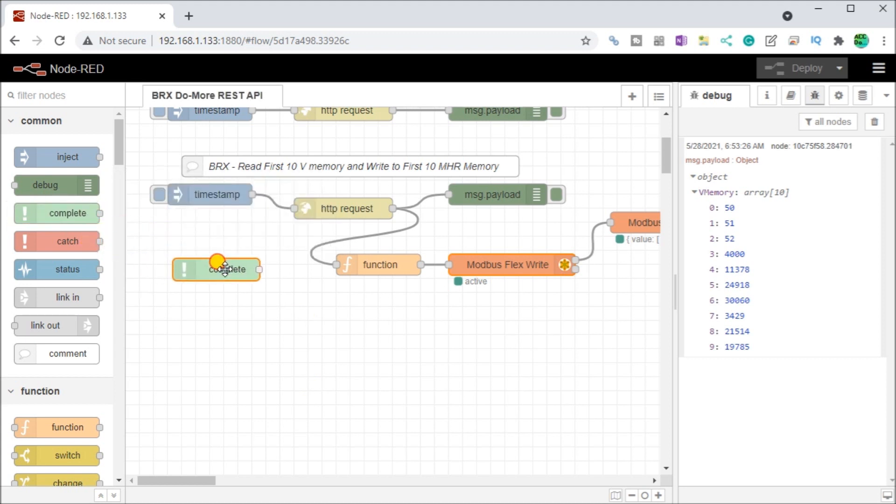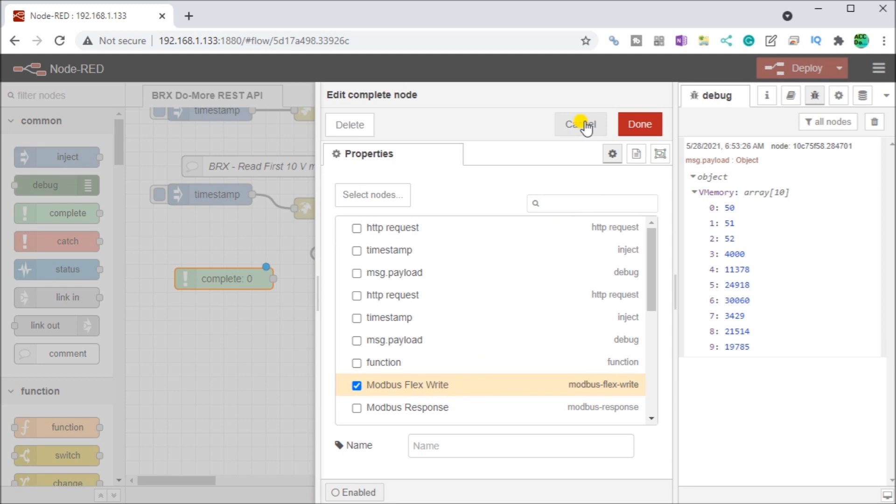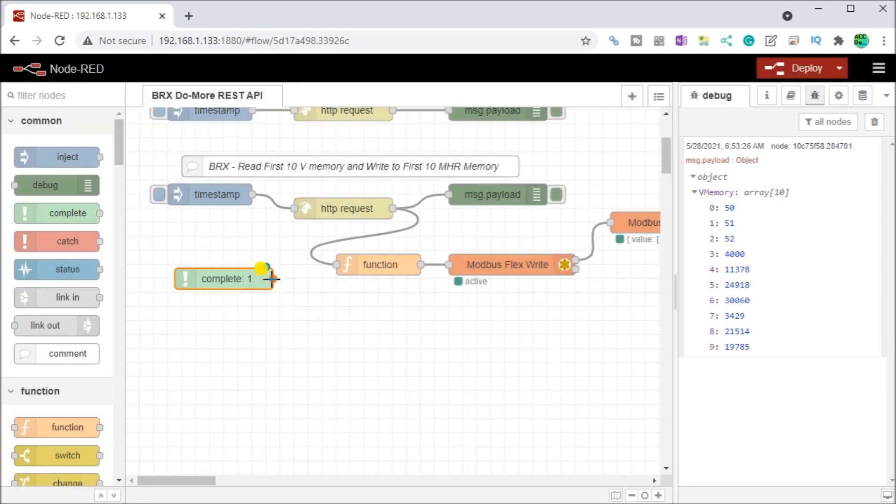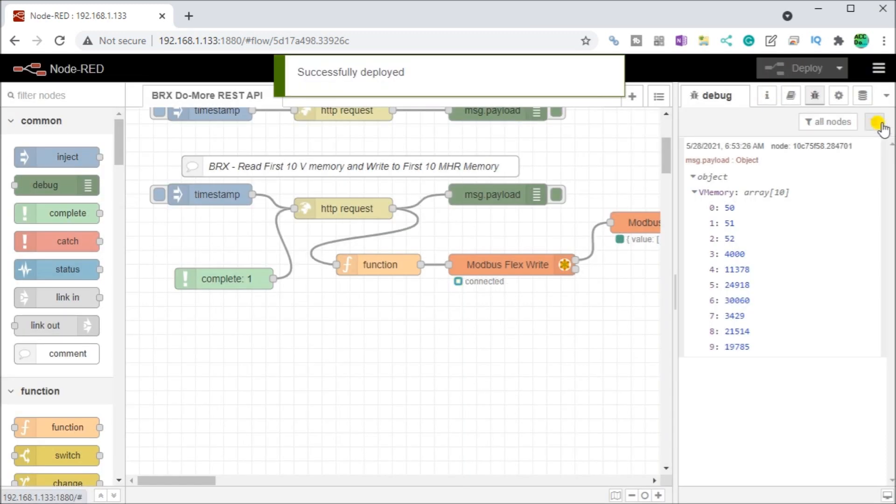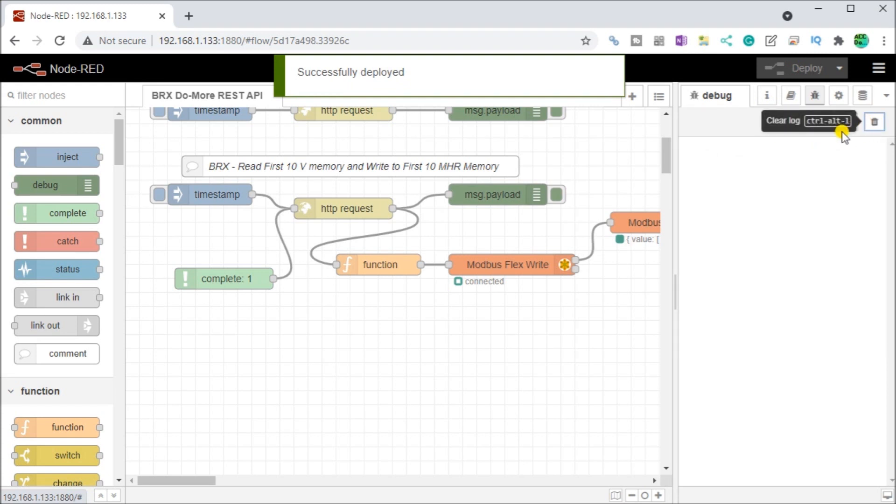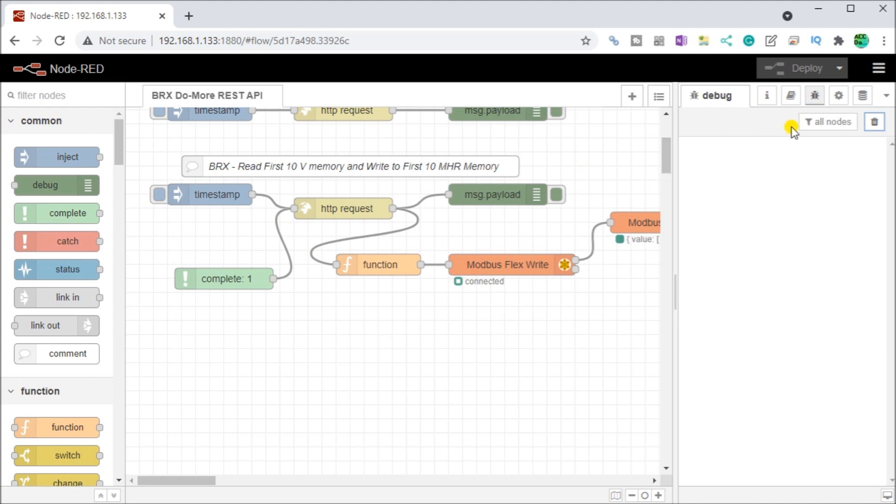If we want to change them all the time, what we can do is we can add a complete on here. Once we've completed our Modbus Flex write, what we want to do is go back and request again. So we can easily do that. Once we have that done, then what we can do is go back and request this again. And now what this will do, we'll deploy that. What this will do then is go through here, request, do the function, do the write. After that's completed, it triggers that again, which does a request and back again. So it continuously updates our values once we've started it.